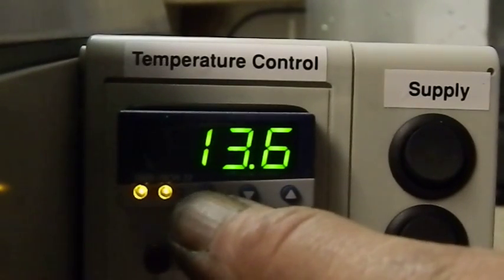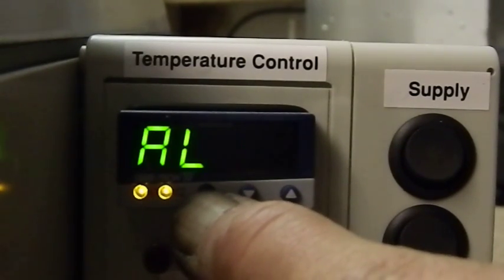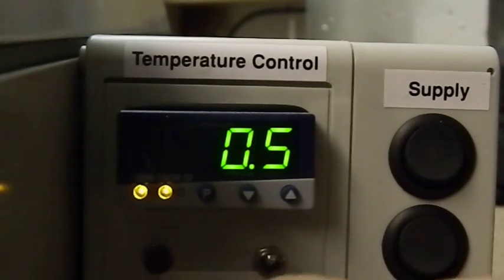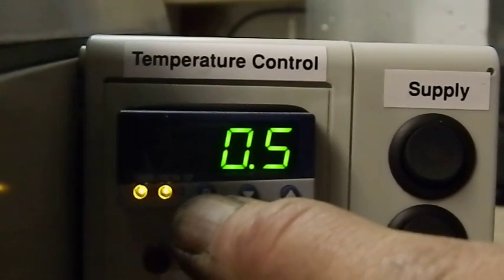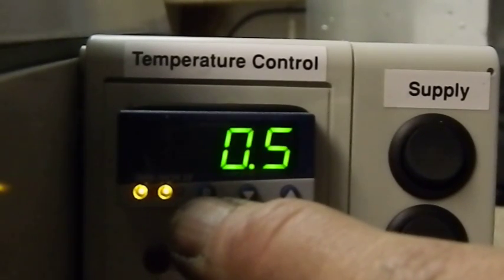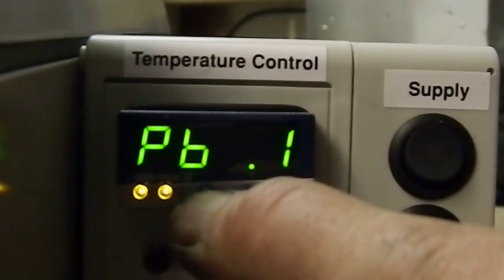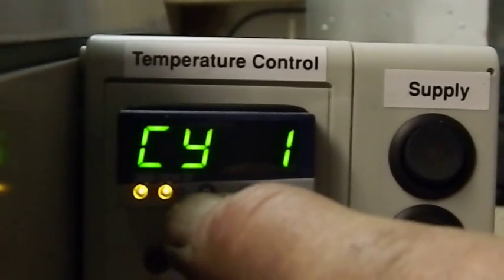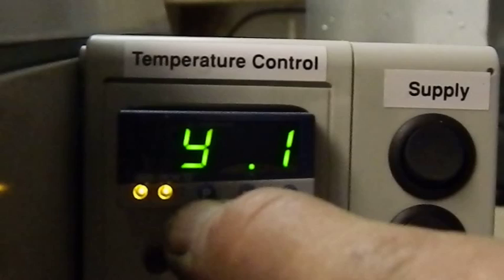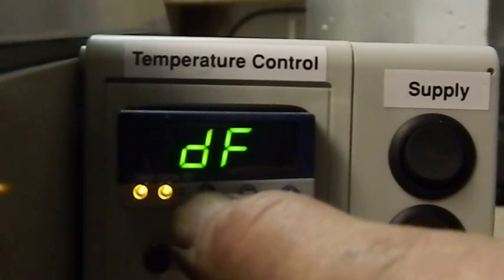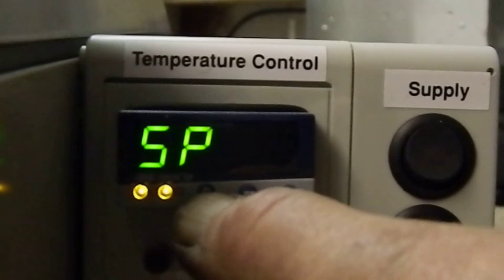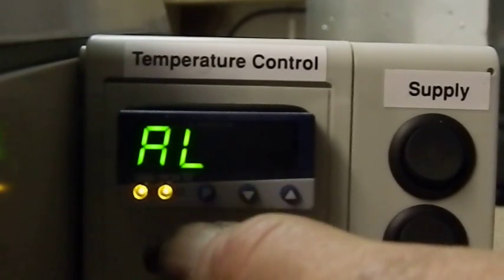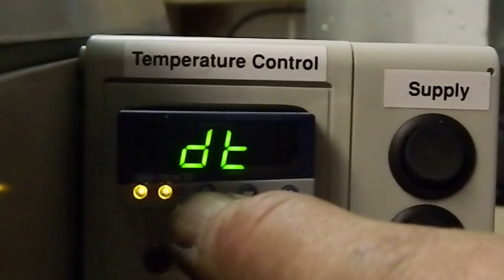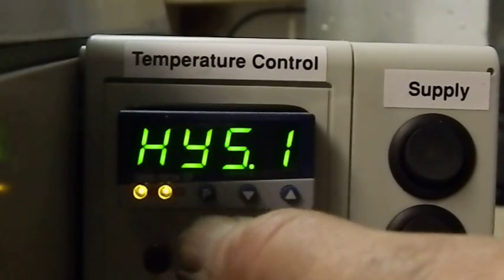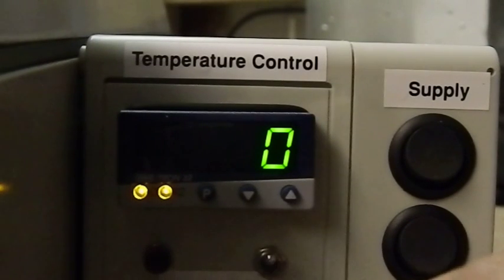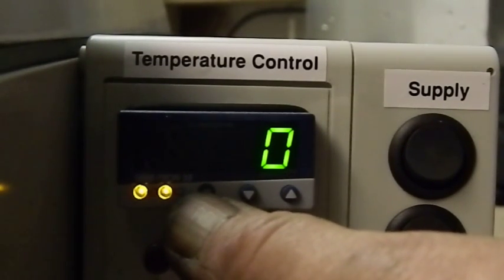So to do this, you press and hold the P button, the left hand button of the three, which brings you to the AL parameter. None of these want to be changed at this point. We need to go through to find the calibration procedure. To do that, press and release the P button a number of times until you reach Y0, which I've just gone past. Okay, press and hold the P button. We do that again. Okay, to AL. You go through until you find Y0. Once you reach Y0, press and hold the P button.